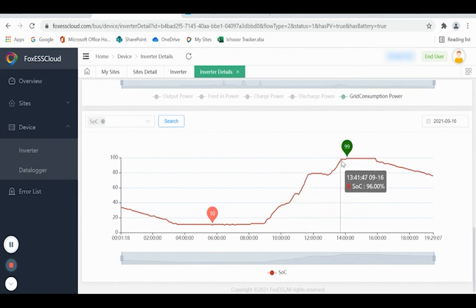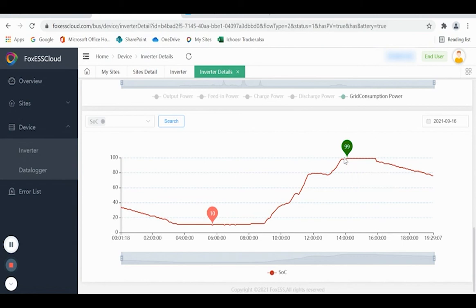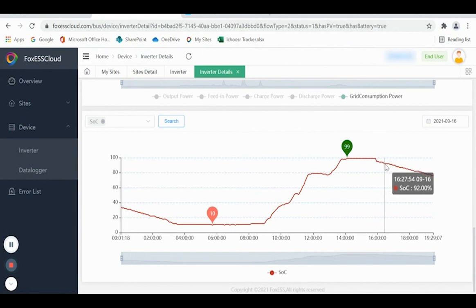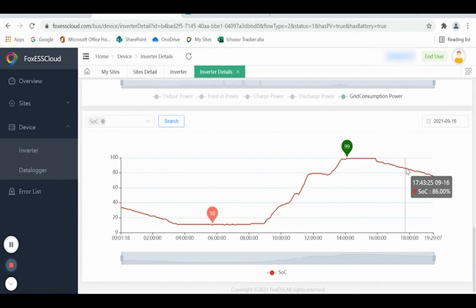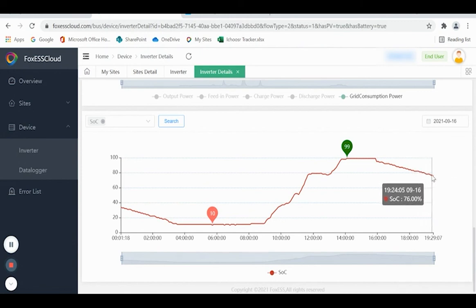Until eventually, at around 2 o'clock, the battery was full. This is the point in time when energy starts to be exported to the grid. Later in the afternoon, at around 4 o'clock in this particular day, you can see the battery charge starts to deplete. This is as the energy from the PV falls away and the demand from the house needs to be picked up by the battery system. As long as this is above 10%, the battery will continue to support the load in the house without any call on the grid.